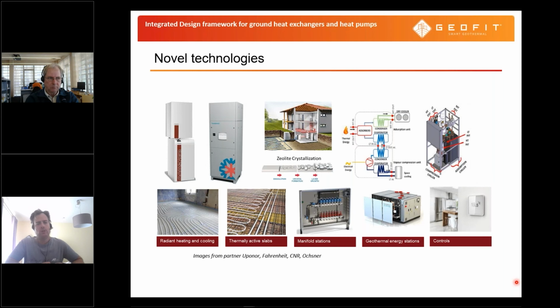So our approach from the R&D partners is this model-based approach, which allows us, depending on how good our models are, to do a precise and accurate component design. And it also makes us capable to establish control strategies, not only for the heat pump itself, but also for the entire system, going from the ground heat exchanger to the heat pump to the building. So we have the entire system, and it should help to minimize risks for not properly working heat pump systems.